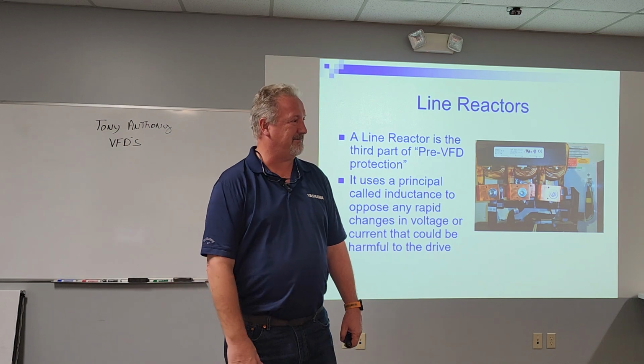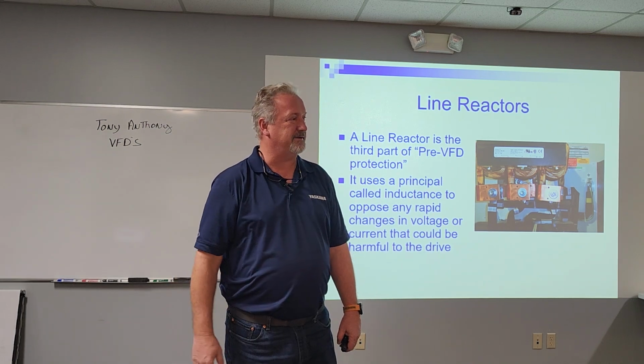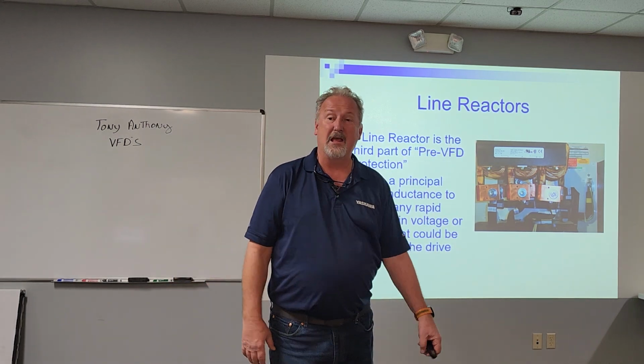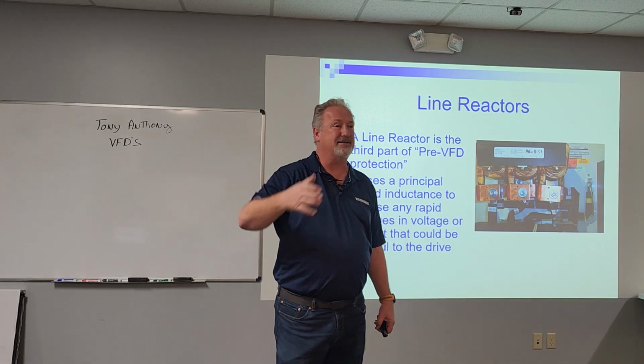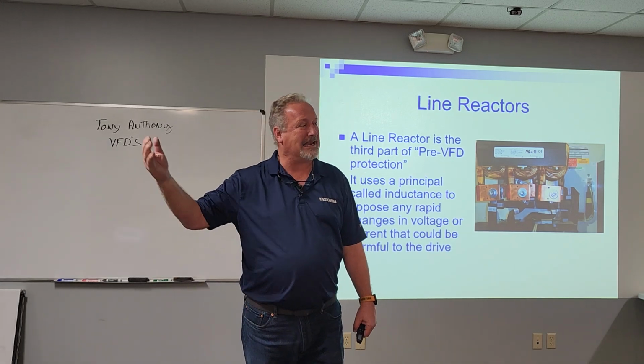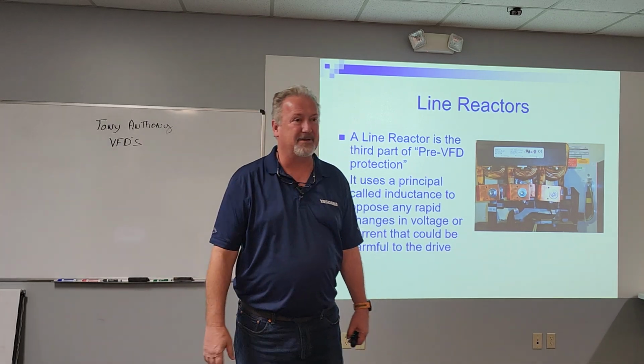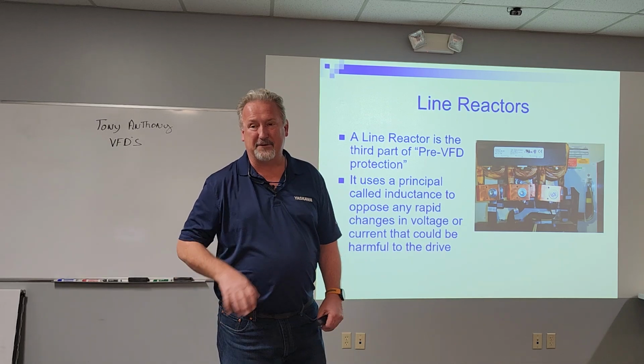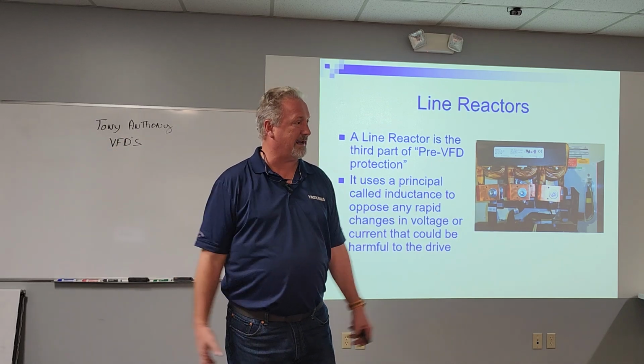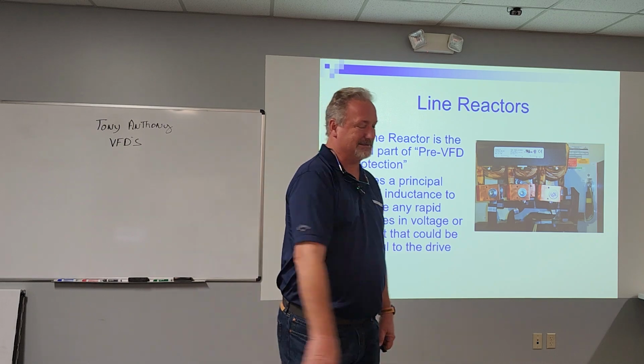But then you get 10 guys topping off. Maybe 10 pumps away, somebody fills it, but you still don't feel it at the other end. But all of a sudden, you just keep adding drives, more people topping off their tank. So if you got 90 people topping their tank off at the same time, guess what you're going to feel? You're going to feel it. That transformer can no longer absorb it and handle it. That's kind of what harmonics is.